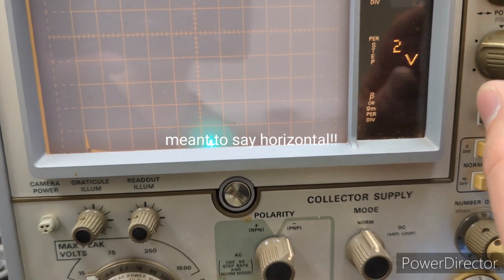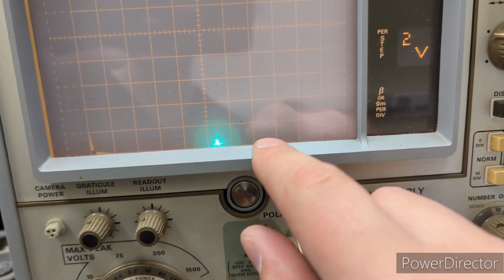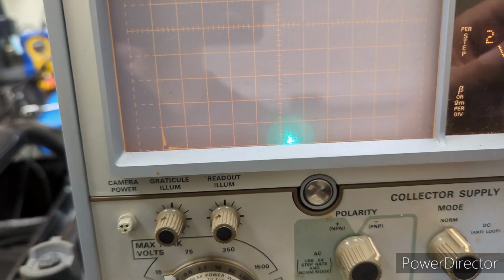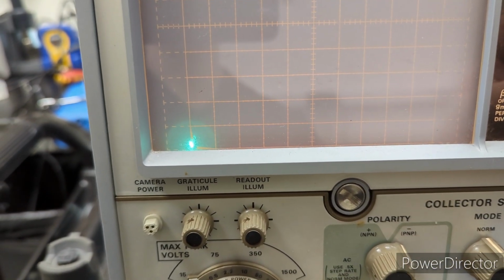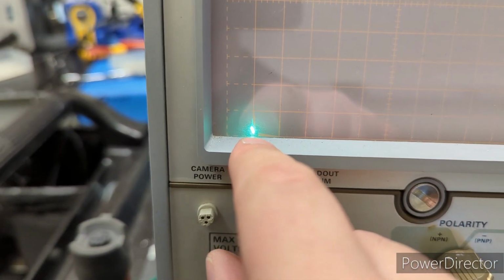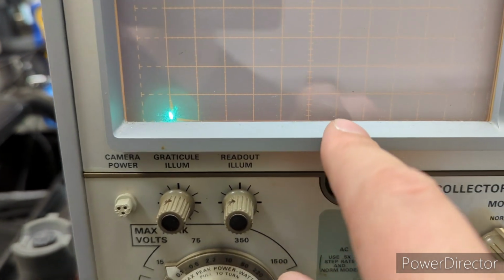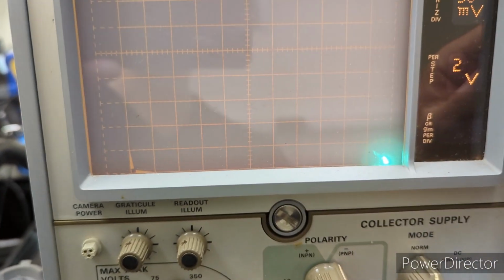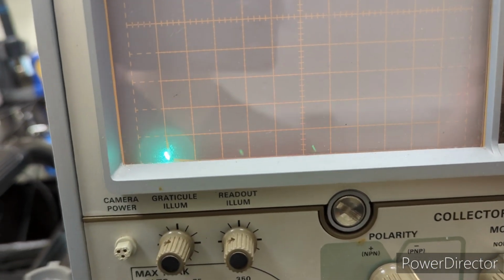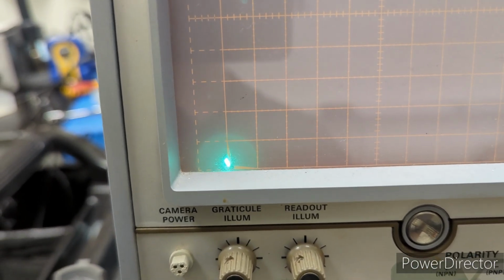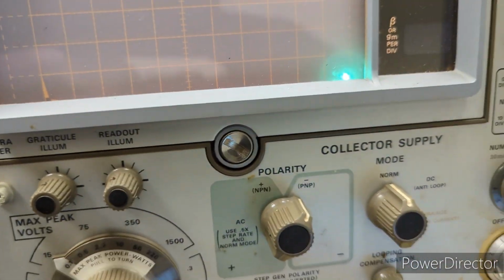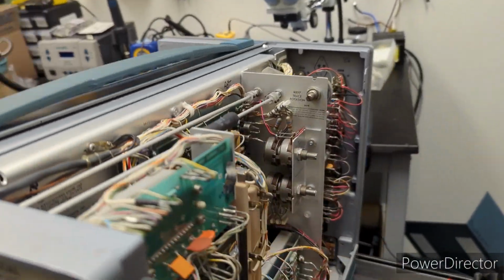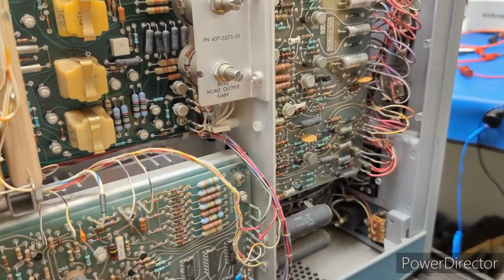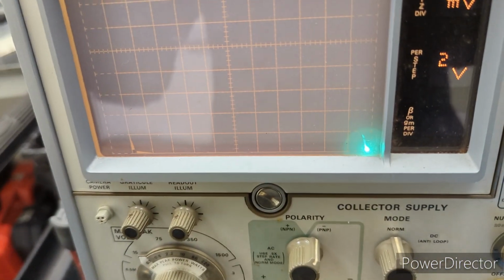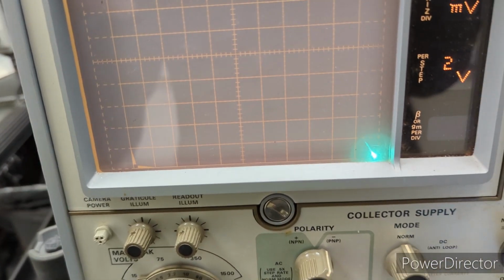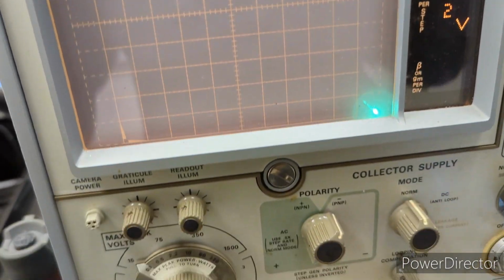Now for the horizontal, you can see 1, 2, 3, 4, 5, almost 5.5. It's now where it should be for NPN, but if we're starting all the way out here, how's it getting to where it should be for the NPN position? I don't know if that's an indication of something with the horizontal gain knob potentially, or some other adjustment that needs to be made, but I just wanted to notate that as well.